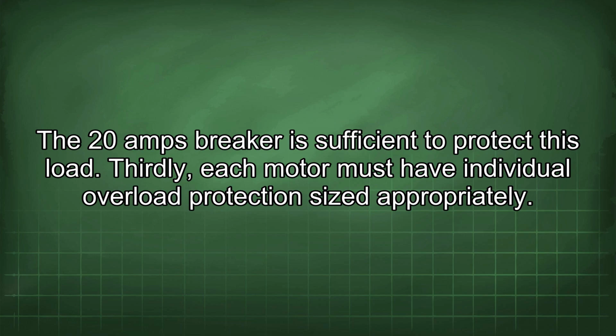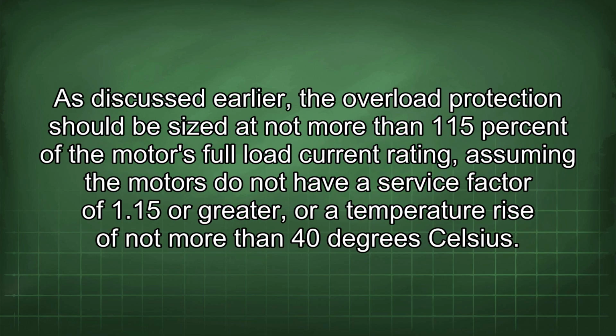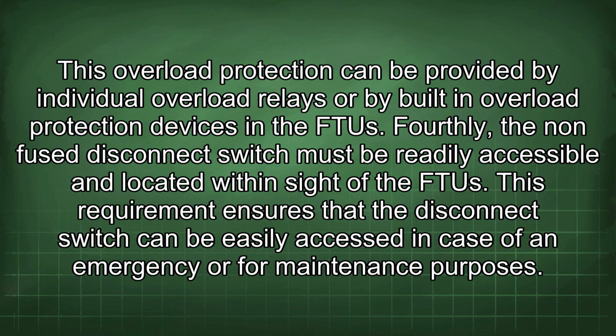Thirdly, each motor must have individual overload protection sized appropriately. As discussed earlier, the overload protection should be sized at not more than 115% of the motor's full load current rating, assuming the motors do not have a service factor of 1.15 or greater, or a temperature rise of not more than 40 degrees Celsius. This overload protection can be provided by individual overload relays or by built-in overload protection devices in the FTU.